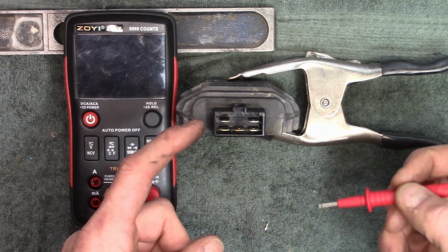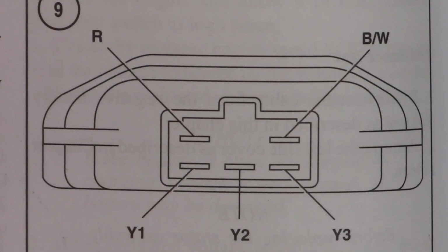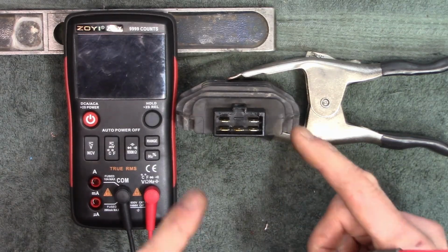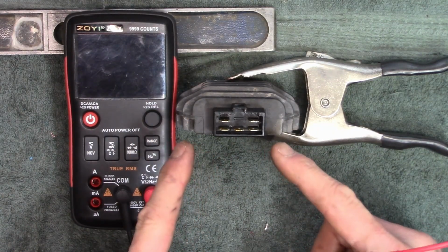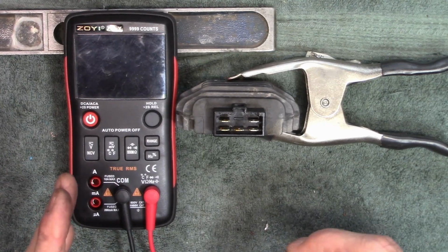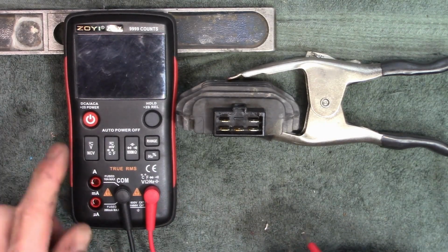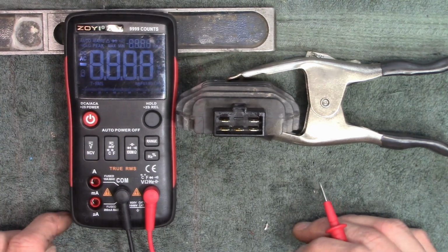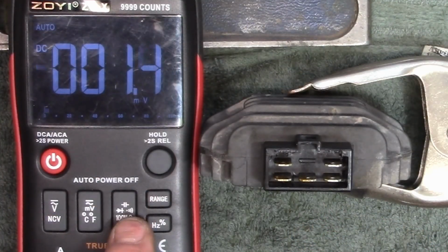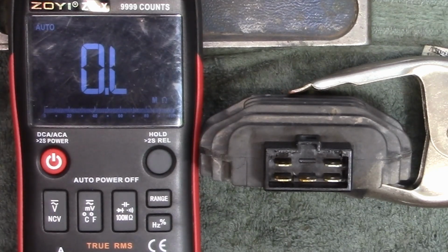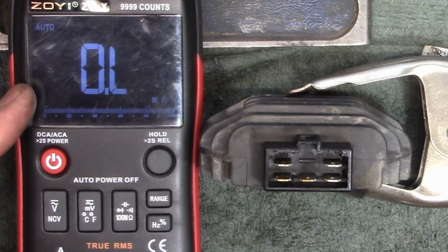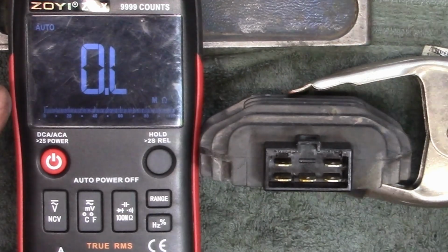These are listed as R, BW, Y1, Y2, and Y3 within the connectors, and each one has different values, but they range between 1 and 20 ohms. So when you turn on your multimeter and select the ohm scale, if it's not auto-ranging like mine, you need to be able to read between 1 and 20 ohms, so you'll need to select the correct range.